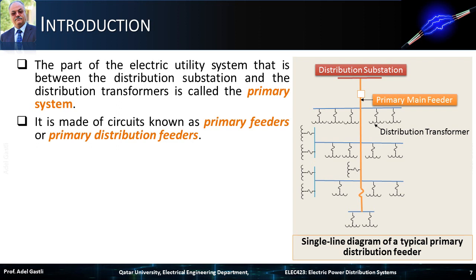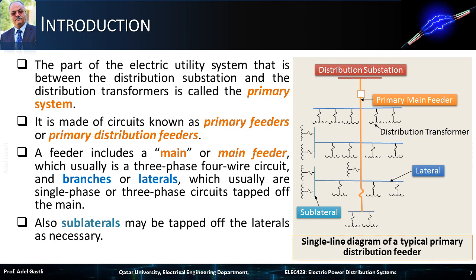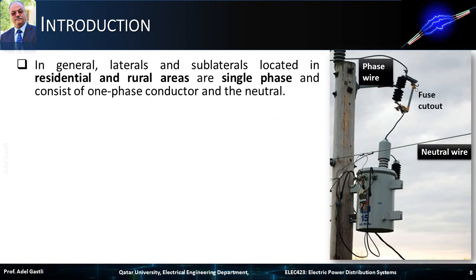It is made of circuits known as primary feeders or primary distribution feeders. A feeder includes a main feeder, which usually is a three-phase four-wire circuit. Branches or laterals, which usually are single-phase or three-phase circuits, are tapped off the main. Also, sublaterals may be tapped off the laterals as necessary. In general, laterals and sublaterals located in residential and rural areas are single-phase, and consist of one-phase conductor and the neutral.